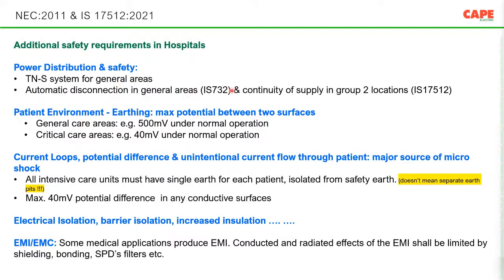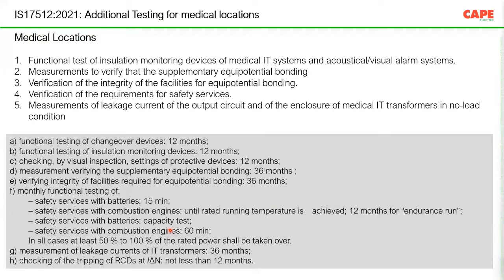Automatic disconnections are necessary. Then there are special requirements for group 2 locations. Then the touch voltage under normal conditions needs to be tested. Then the current loops: for example, when you operate some equipment which creates a kind of leakage current, or sometimes some electromagnetic influences, parallel paths may also have a current flow which can create problems. So all these things must be tested. EMI has to be under control, otherwise your electrical communication system will create problems. And the last one for the medical location is the additional test. In a normal electrical installation, you need to have the 10 different tests, and in the medical location, you need to have the additional test.